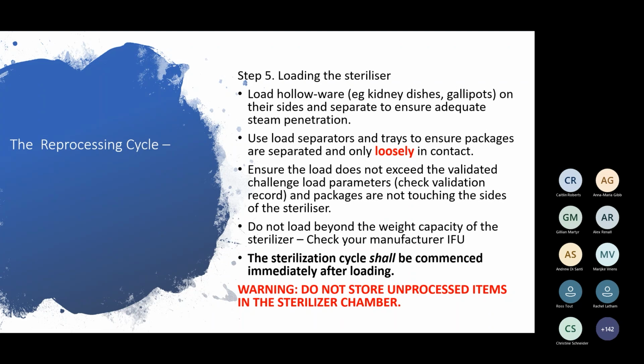Ensure the load does not exceed the validated challenge load parameters. So check your validation records and packages are not touching the sides of the sterilizer. Do not load beyond the weight capacity of the sterilizer. So make sure you check your instructions for use on your sterilizer to see what your machine is capable of doing. And this is really important: the sterilizing cycle shall be commenced immediately after loading.